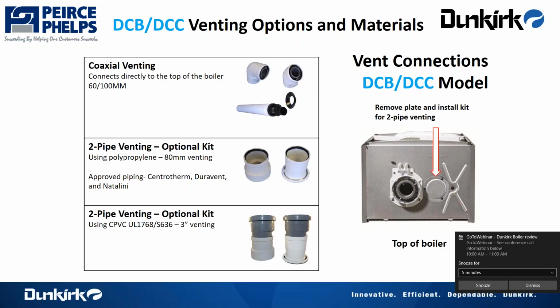We also have a 2-pipe venting system that we can utilize, an 80 millimeter polypropylene, or we can also utilize a 2-pipe venting system of CPVC vent pipe. On the right, we see the top of the boiler. The boiler comes with the coaxial hookup on it. Again, if we're utilizing it that way, we're ready to go. If you're utilizing a 2-pipe system, there are adapters that you use, and your combustion air would come in where that plate is shown on the right at the top of the boiler.